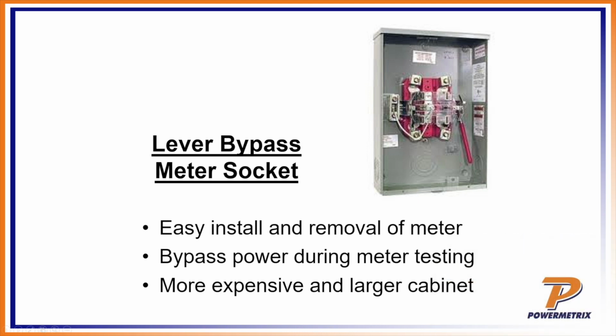So you've got lever bypass. It's an easy install and removal of the meter, and it bypasses the power during the meter testing, but it's a more expensive and larger cabinet. Okay, this all boils down to the ease of removal of the meter, much easier and safer with this lever bypass, because we know that we've bypassed the power, so I can feel a lot safer removing and installing a meter when I've got the lever bypass.